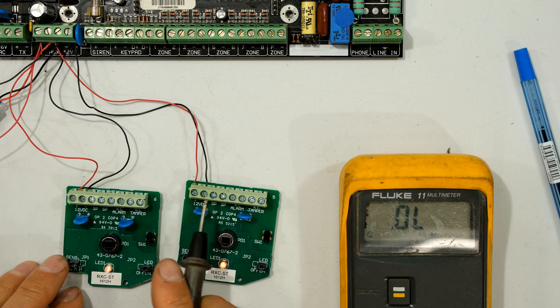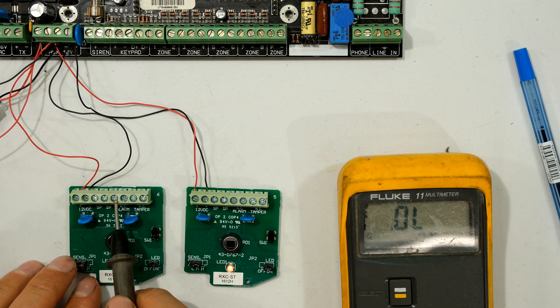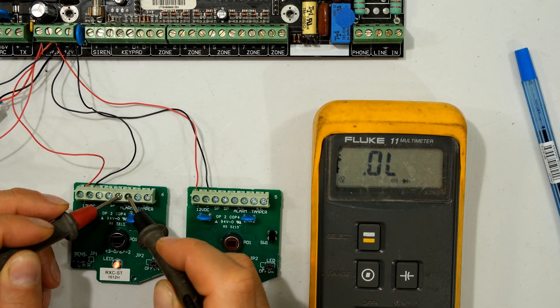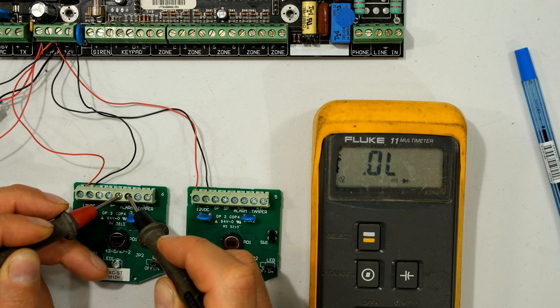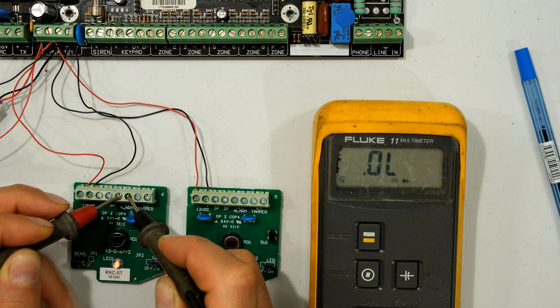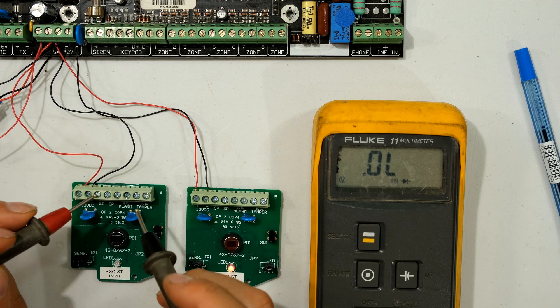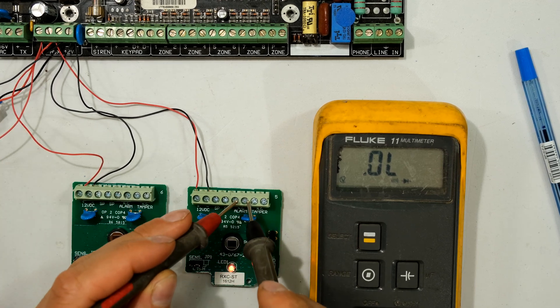Now let's look at the two faulty units. Positive, negative, normally closed on these terminals. I put my leads across the normally closed - the meter says OL. The sensor has operated, and when I put my finger there it has operated again, but now it should show as normally closed and these terminals are not working at all.